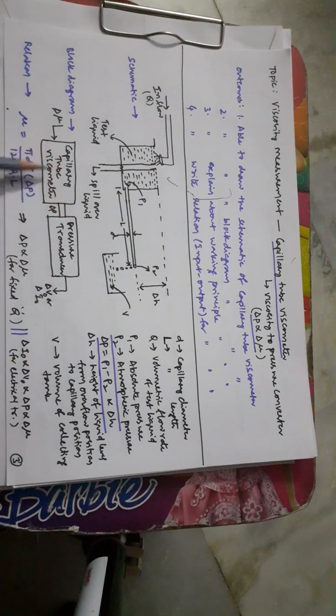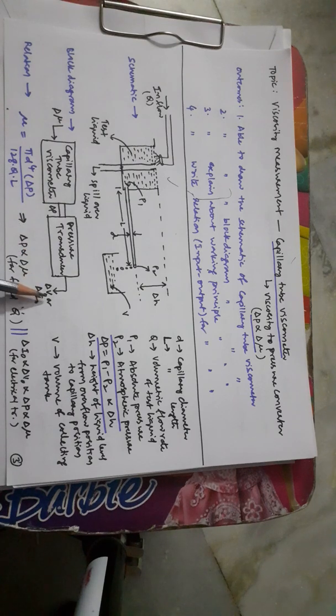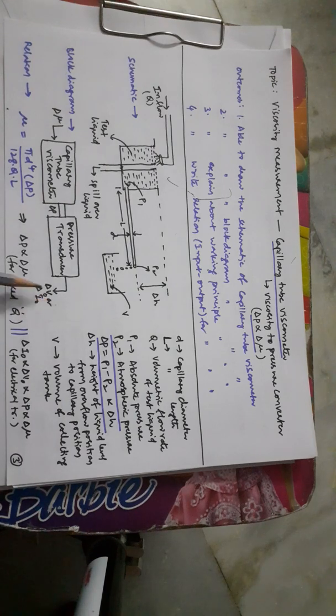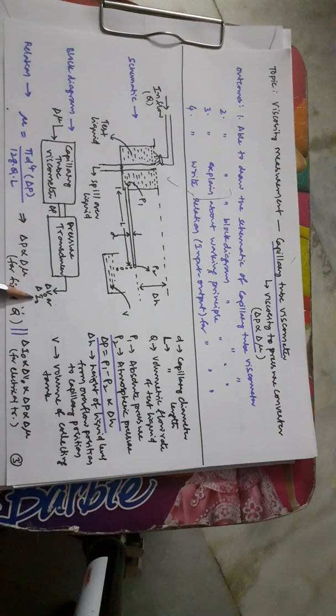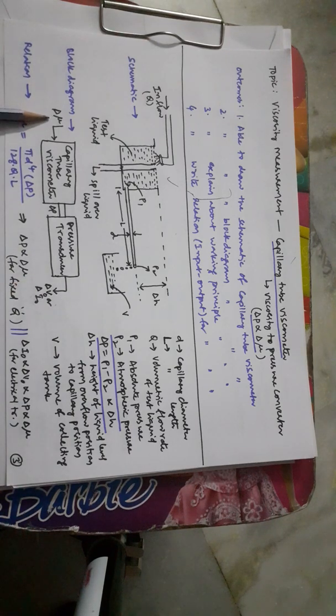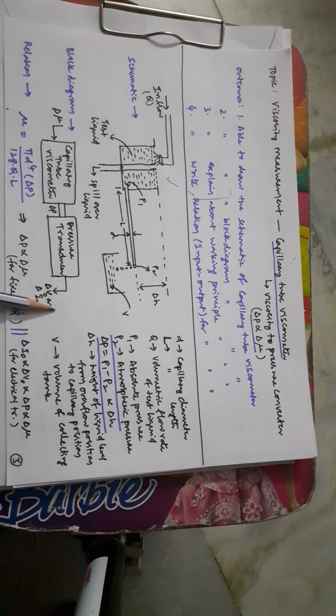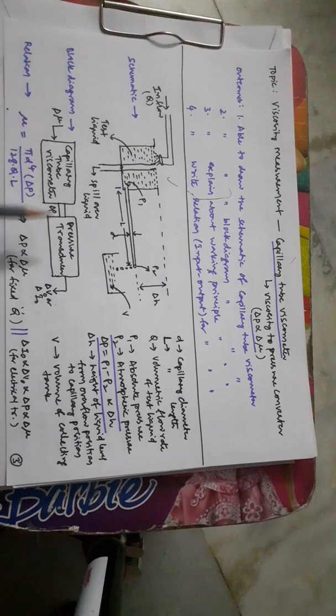The required output voltage range after proper amplification is typically 0 to 5 volts, and when recording current the range is 4 milliamperes to 20 milliamperes. Ultimately, the current or voltage output must be proportional to the input being measured. A digital panel meter displays either voltage or current, and these values are calibrated in terms of the input quantity.